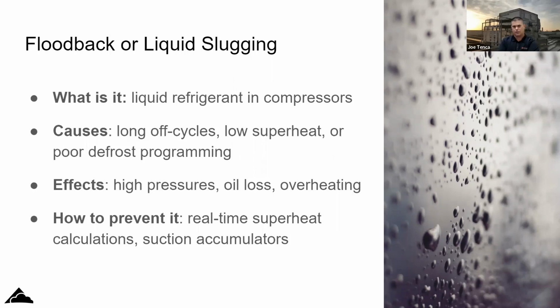If a compressor is off on an oil failure, then something did happen, whether it ran out of oil, or there was liquid contaminating the refrigerant so it was thinned out and lost its pressure. Sometimes you've got to go back and do more research. Especially nowadays with the technology out there, you can look through the computers and the controls and look at suction temps and systems coming out of defrost, to figure out if there's a possibility of liquid floodback at one point.